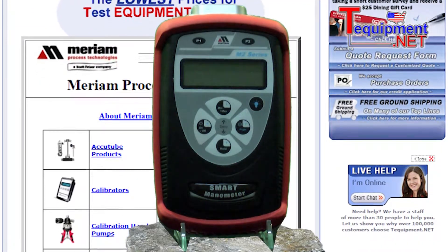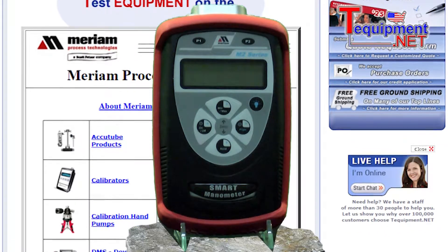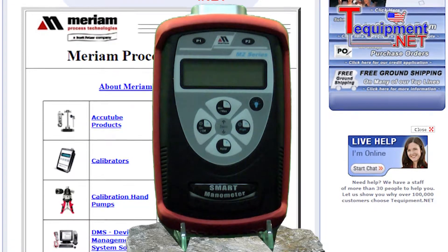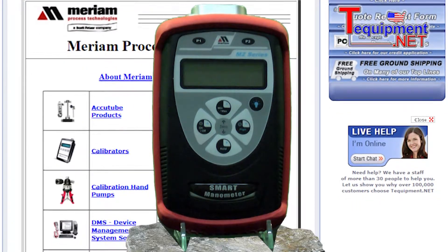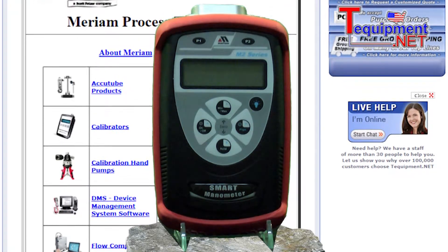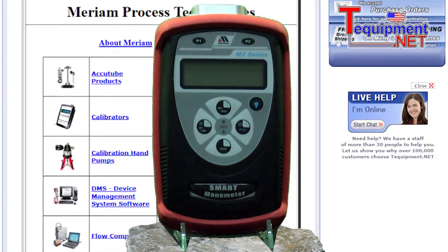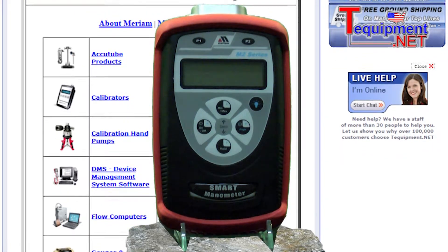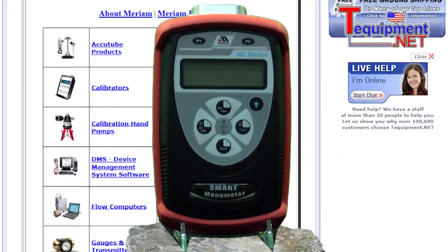Meriam's M200 series smart manometers bring high precision and value to handheld digital manometer users. The M200 features NIST traceable accuracy of ±0.025% of full scale, independent of temperature effect, with pressure ranges from 0–28 inches of water to 0–2000 psig of full scale.